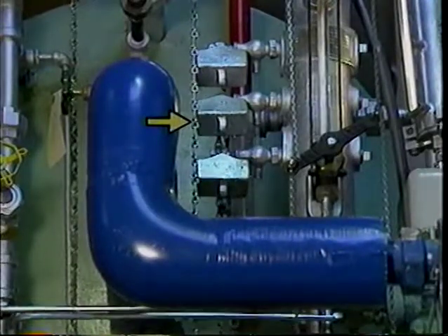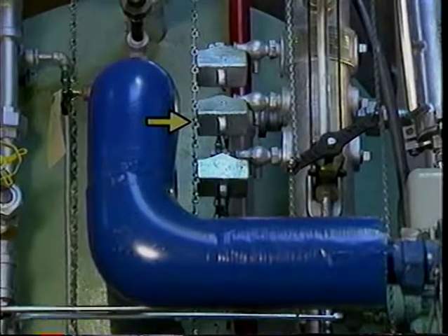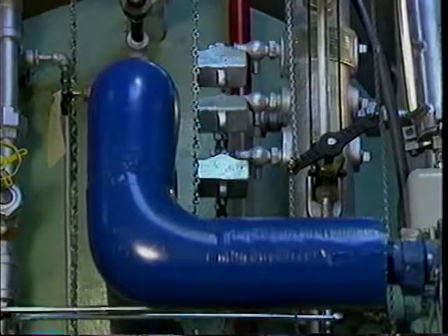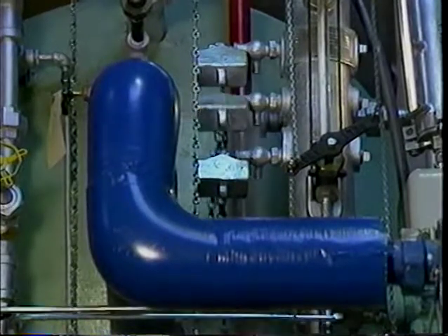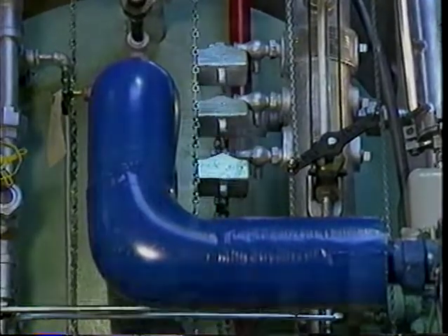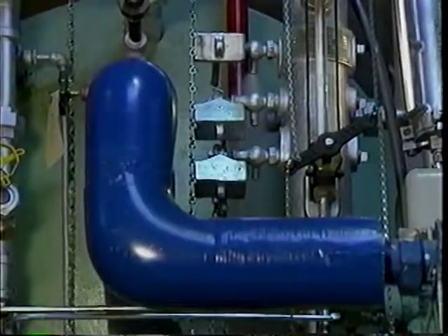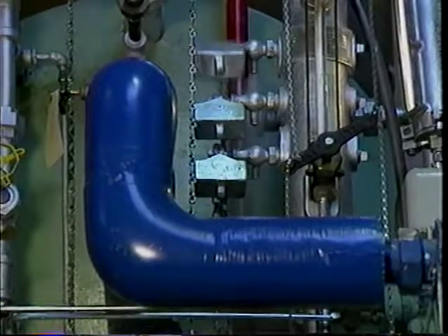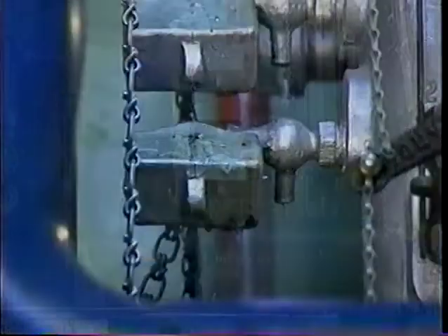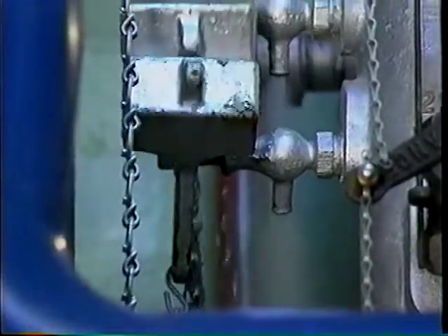The middle tricock is located at the NOWL. If water comes out of the middle tricock, the gauge glass is functioning properly. If water comes out of the top tricock, there is a high water condition in the boiler. If water comes out of the bottom tricock, water may be safely added to the boiler.